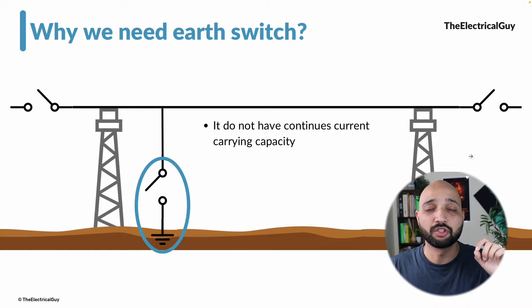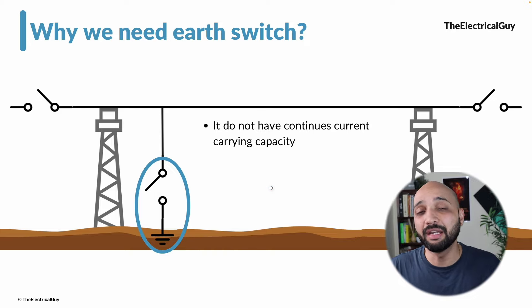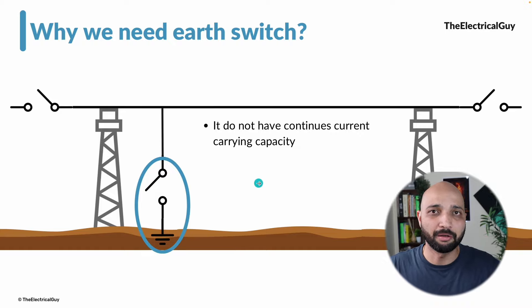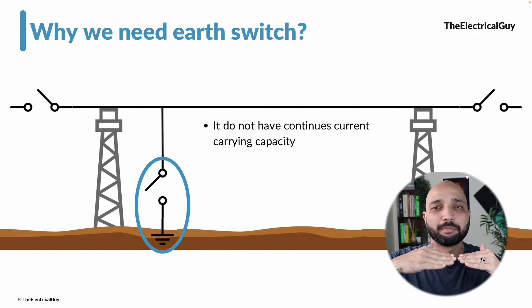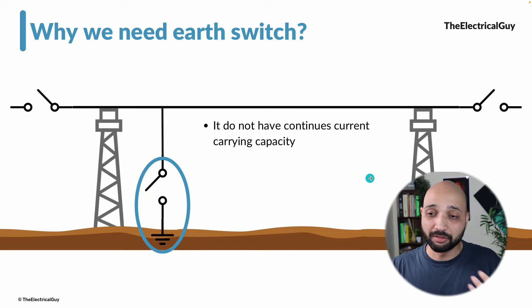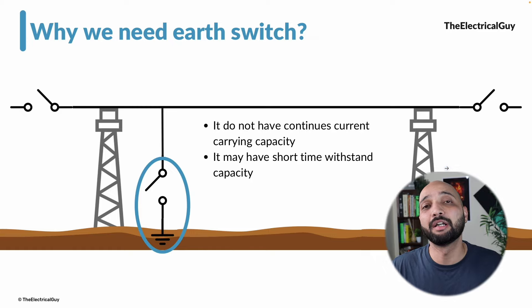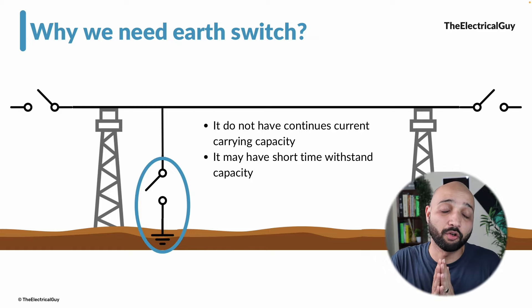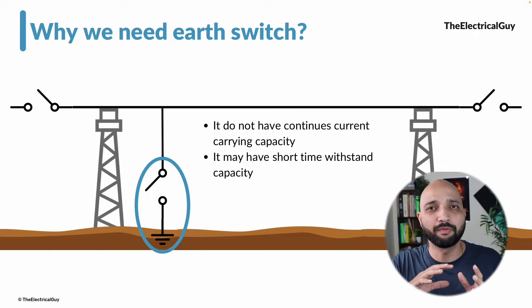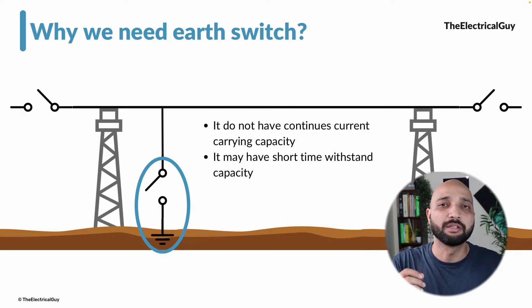There are a few things to know about the earthing switch. First, earthing switches are not closed during normal operating conditions — when the line is live we do not close them. Therefore they do not have any continuous current carrying capacity. If your system current is 2000 amperes, the earth switch is not designed for that. However, the earth switch should have the capability to carry short-time withstand current for a specified duration — such as one second or three seconds — which is essentially the fault current.